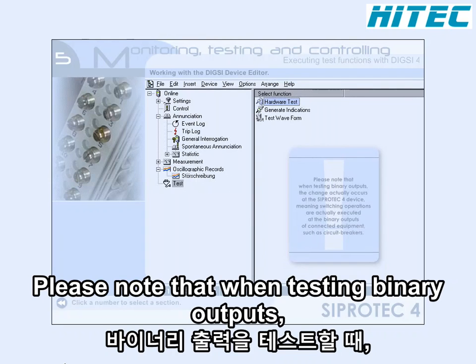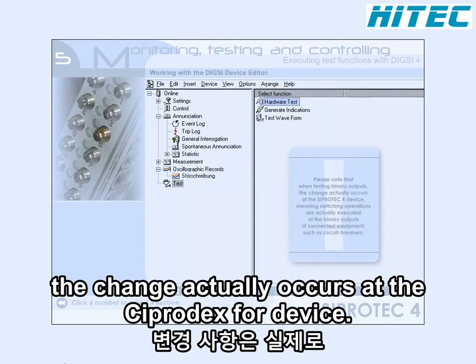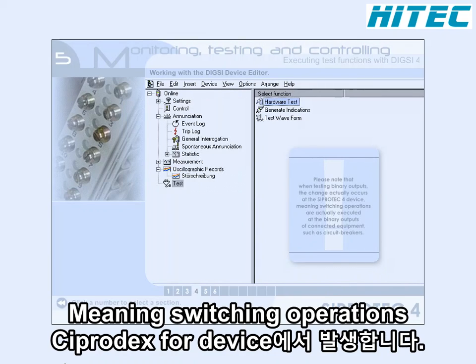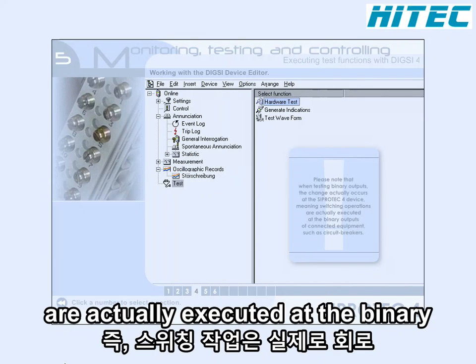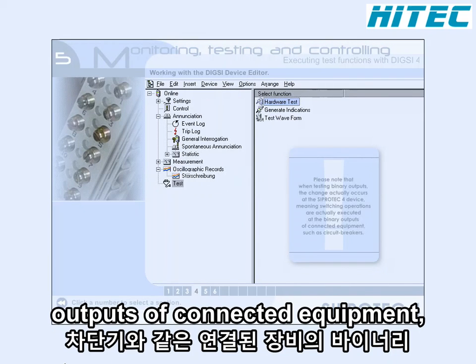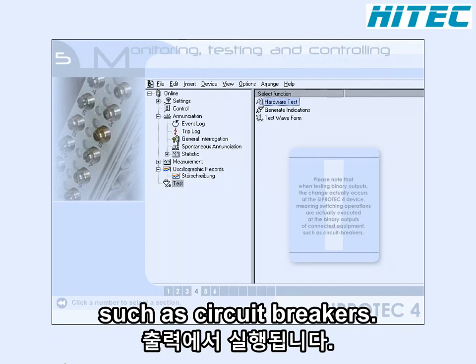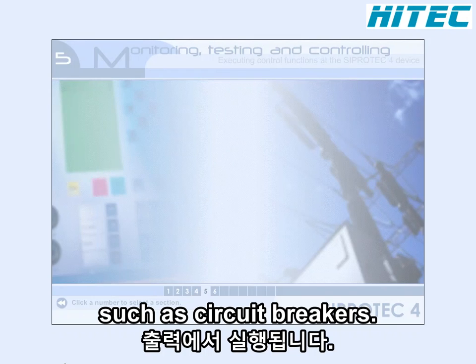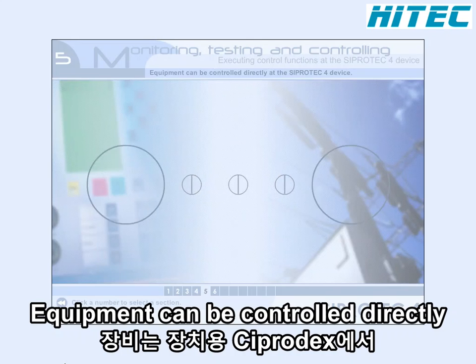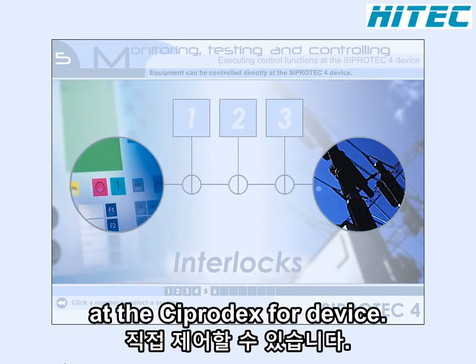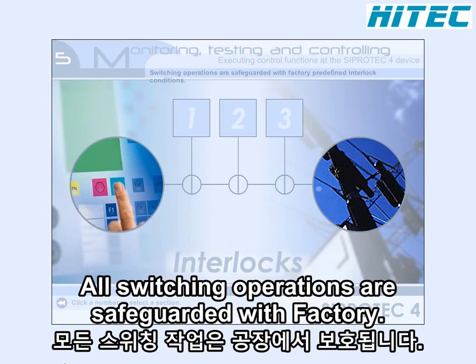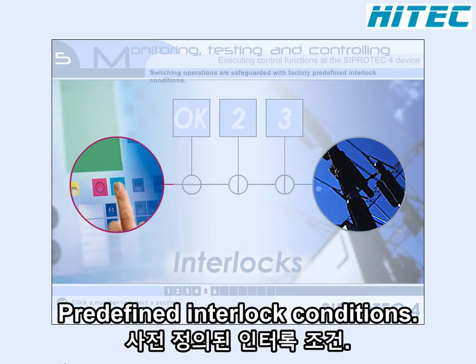Please note that when testing binary outputs, the change actually occurs at the SIPROTEC 4 device, meaning switching operations are actually executed at the binary outputs of connected equipment, such as circuit breakers. Equipment can be controlled directly at the SIPROTEC 4 device. All switching operations are safeguarded with factory predefined interlock conditions.